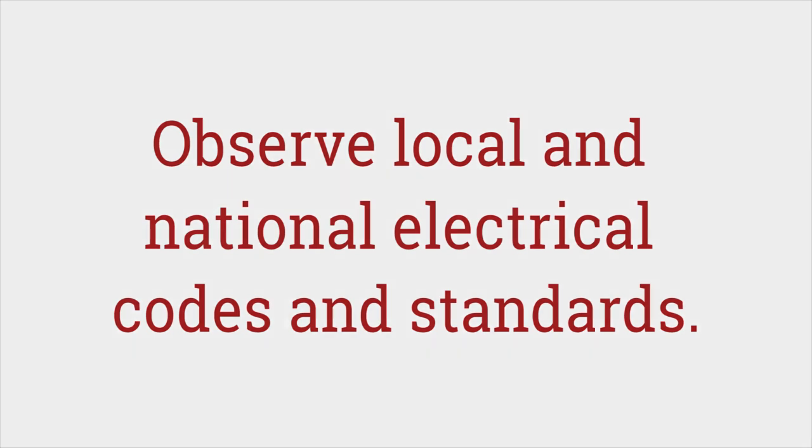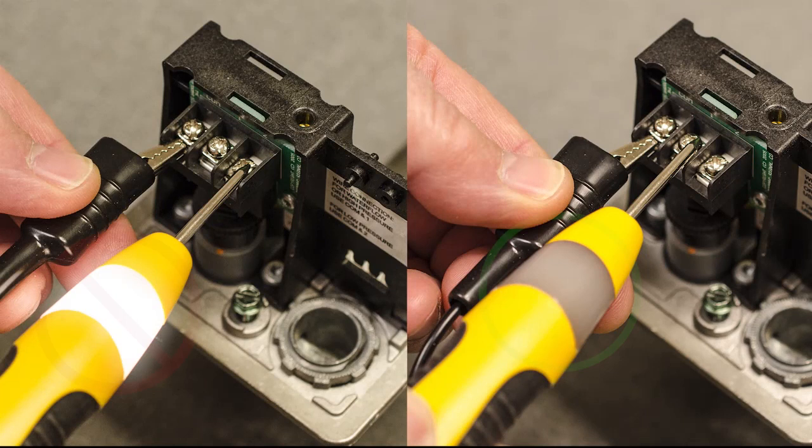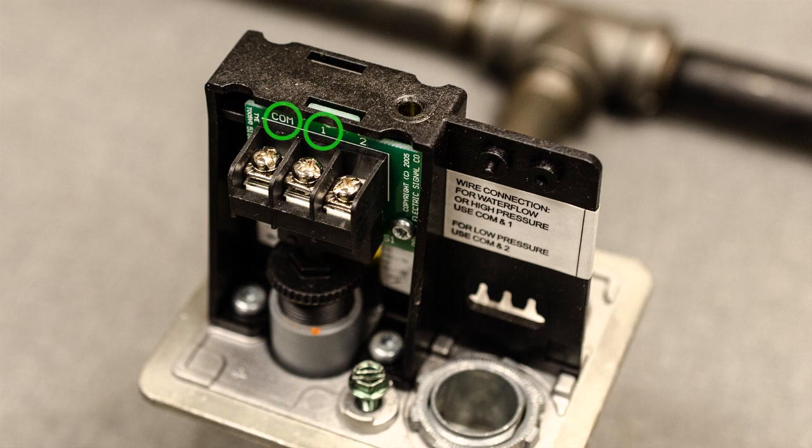Use an ohm meter or continuity tester to make sure you have the normally open switch contacts. These would be the terminals with no continuity when there is no pressure or water flow on the PS10.